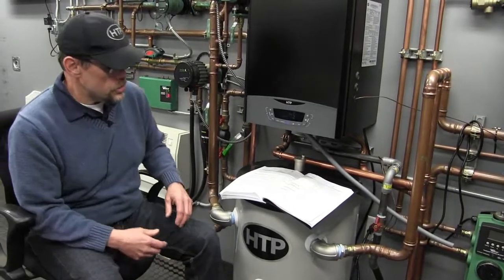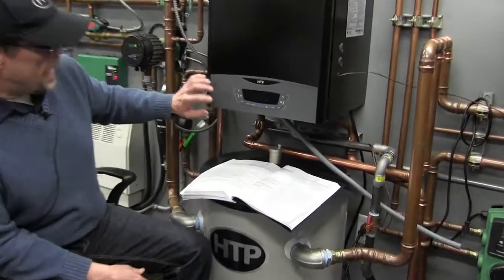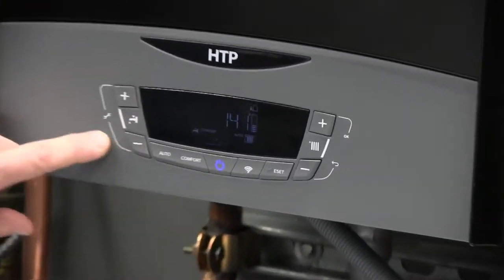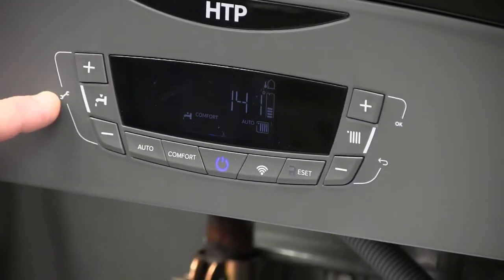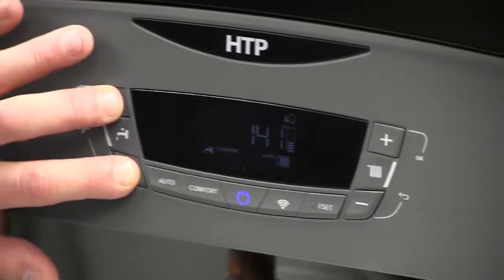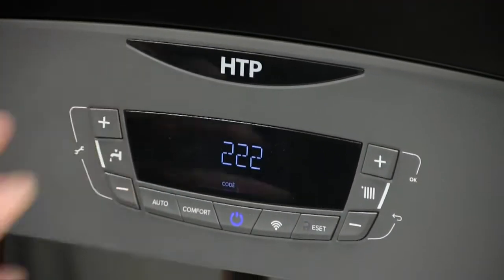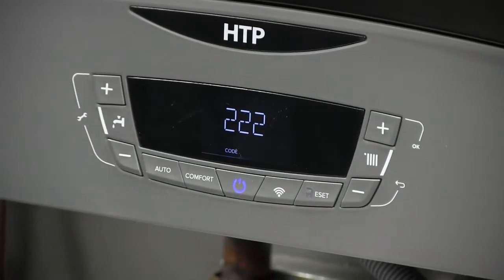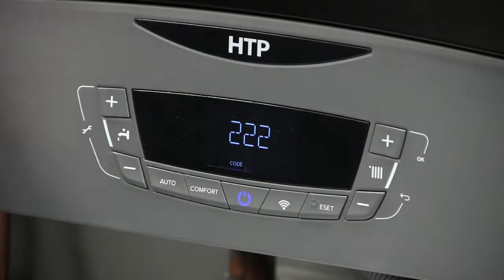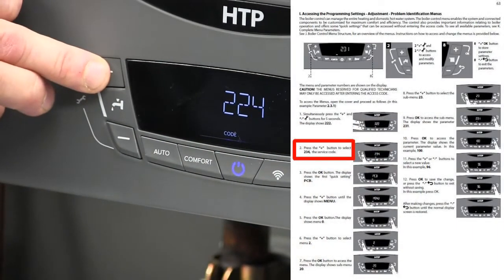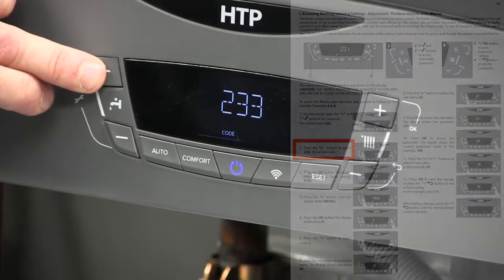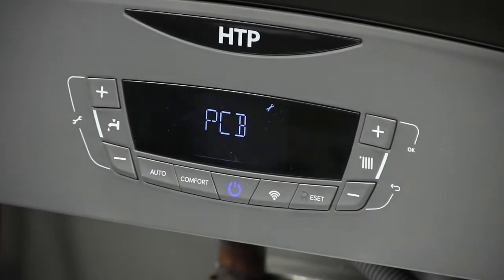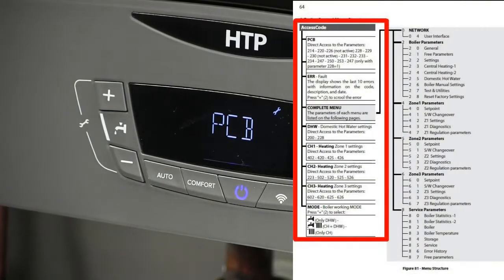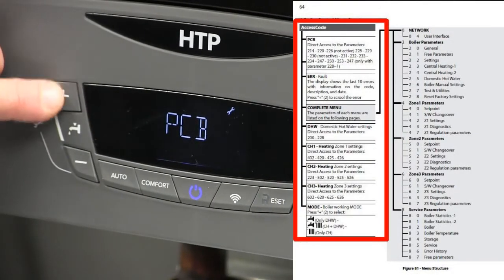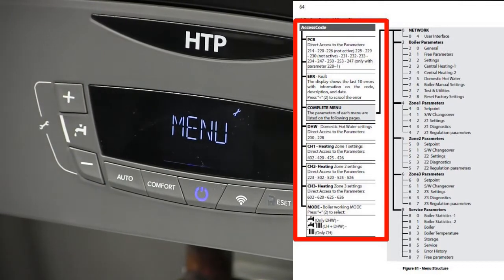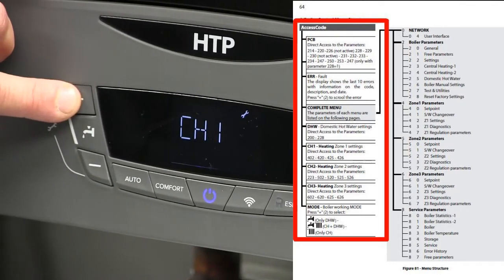So, let's do this. To access our menu, we hit the service wrench, the plus and minus buttons simultaneously, and we have to enter our code to access the control. So we go up to 234, which is the access code. When we get to 234, we hit OK, and that brings us into our quick access. In the quick access, I go to menu. Let me first show you the central heat 1.